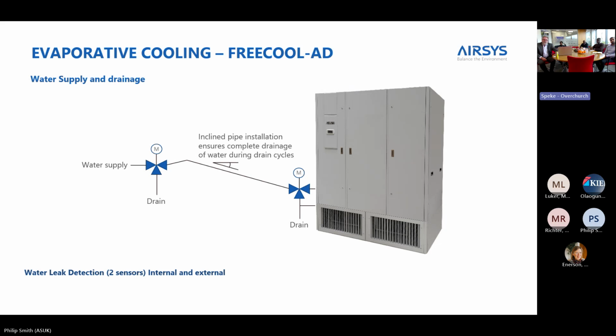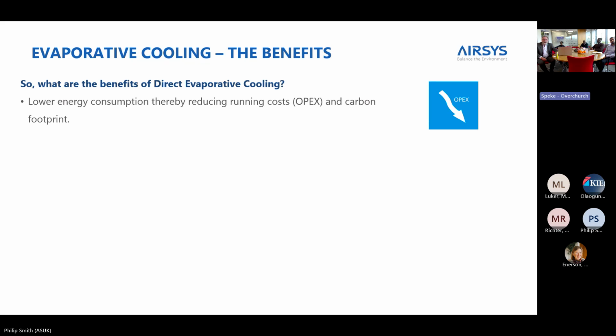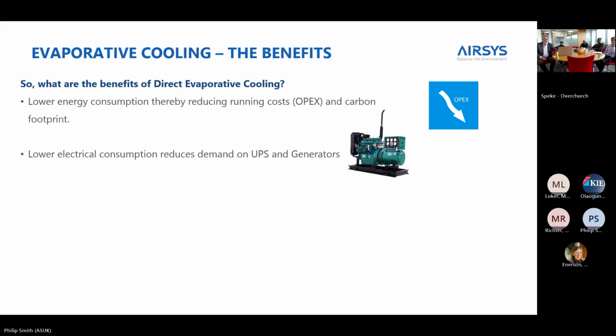Certainly in terms of installing the adiabatic systems, it's a water supply and it's a drain. It's as simple as that. So in terms of energy, really it is just a fan. There is a little bit of water. You can lower your electrical demand on the room. Now, BT use these extensively. And what they do is they remove a DX unit. They put an adiabatic unit in. They release a few kilowatts of heat, of energy that they can then put some more servers in.